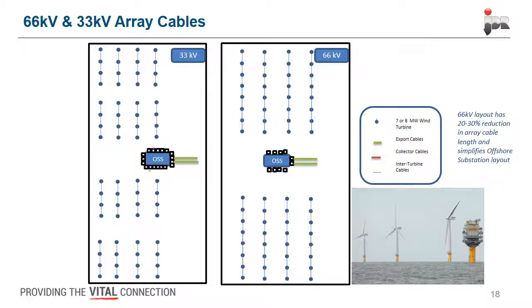So here are two graphics of 2 wind farms. They're both the same. One is linked up with 33 kV cables, and one is linked up by 66 kV cables. In the middle, we've got an offshore substation. Each of these dots is a wind turbine. And at 33 kV, with typically 7 or 8 megawatt turbines, you can get economically typically 4 turbines onto a string. Whereas if you increase the transmission up to 66 kV, you can get 8.